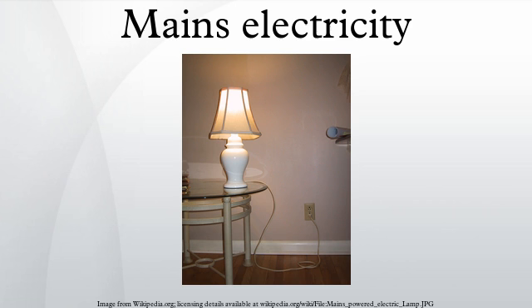Measuring voltage: a distinction should be made between the voltage at the point of supply and the voltage rating of the equipment. Typically the utilization voltage is 3% to 5% lower than the nominal system voltage. For example, a nominal 208 V supply system will be connected to motors with 200 V on their nameplates. This allows for the voltage drop between equipment and supply.